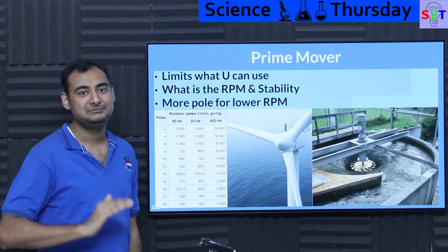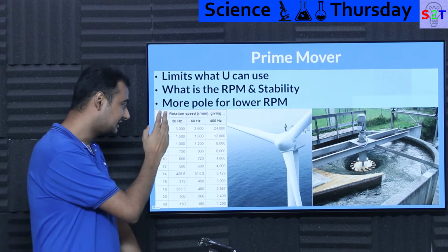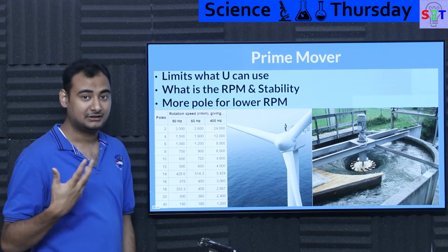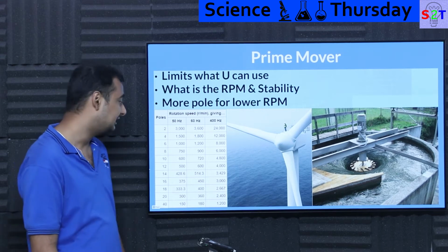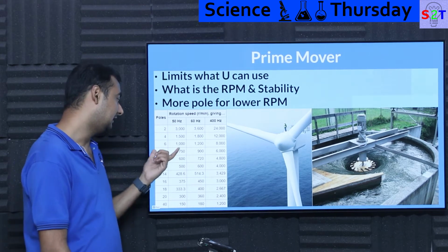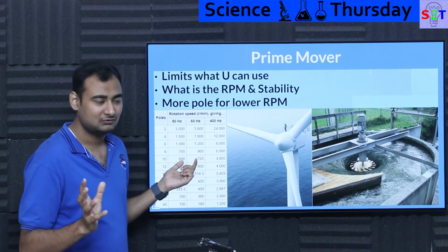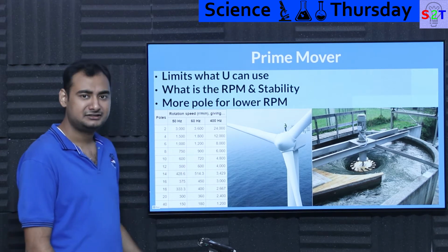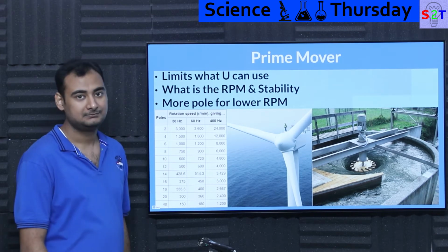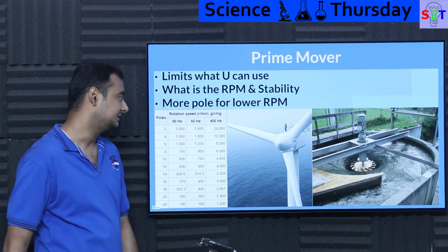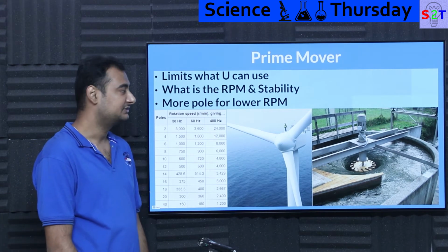More poles generally means lower RPM, so it's up to you, and it translates even to 60 hertz. If your engine can only rev up to, say, 1200 RPM, go with a 6-pole system. If it's a slow watt system, an old diesel generator at 900 RPM, go with 8-pole. You can easily find this RPM to hertz relationship anywhere.